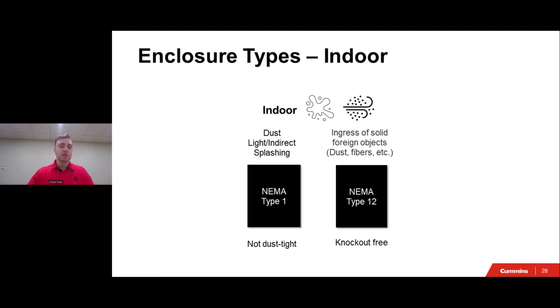So like I just mentioned, let's go ahead and talk about enclosures. Enclosures play an important role into any transfer switch application as they are there to protect your automatic transfer switch from many things. The rating systems for enclosures are defined by NEMA. For indoor applications, you have the NEMA Type 1 and the NEMA Type 12 enclosure, which are there on your screen. I'm going to talk about the Type 1 first. So the Type 1 is a general purpose enclosure that is constructed for indoor use.